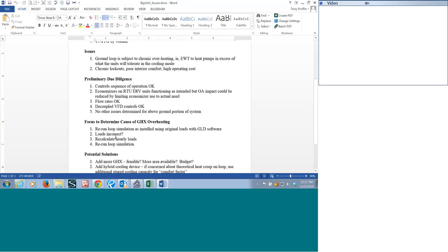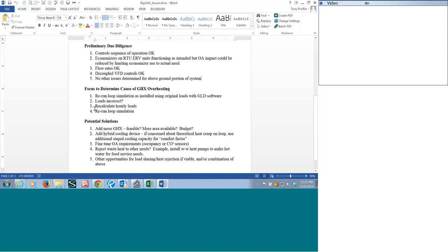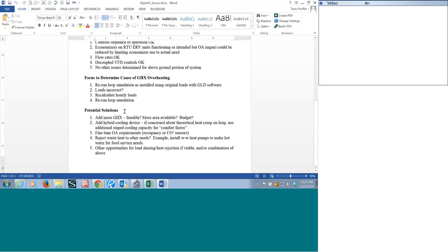But the first or second year is usually where these things will end up if in perpetuity, unless something's going to change. That being said, our 5-year projection is saying we could be up to 116 degrees. It does fit with the complaints from the client in the first year, first summer, that this retail facility was overheating and heat pumps were chronically locking out. So what we've done now is we've recalculated loads. We think we've identified what the issue is. We were undersized. GLD simulation is replicating what's actually occurring, which is a good thing. At least we have direction to go.